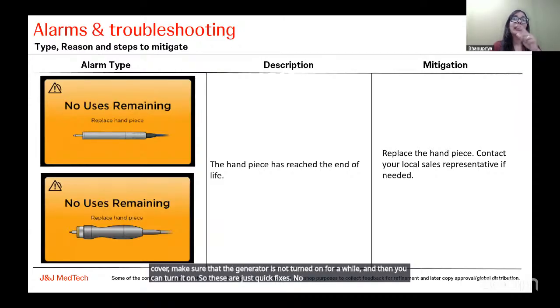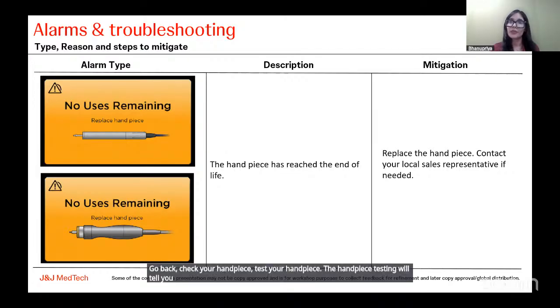No uses remaining. Now, if the error says no uses remaining, I would suggest you go back, check your handpiece, test your handpiece. The handpiece testing will tell you the number of uses remaining.